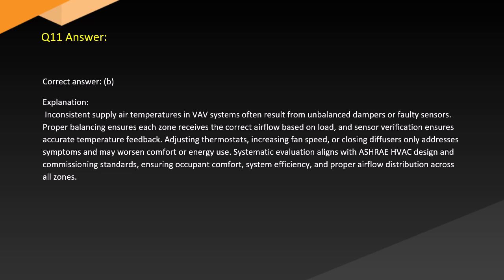Answer. Correct answer: B. Explanation. Inconsistent supply air temperatures in VAV systems often result from unbalanced dampers or faulty sensors. Proper balancing ensures each zone receives the correct airflow based on load, and sensor verification ensures accurate temperature feedback. Adjusting thermostats, increasing fan speed, or closing diffusers only addresses symptoms and may worsen comfort or energy use.